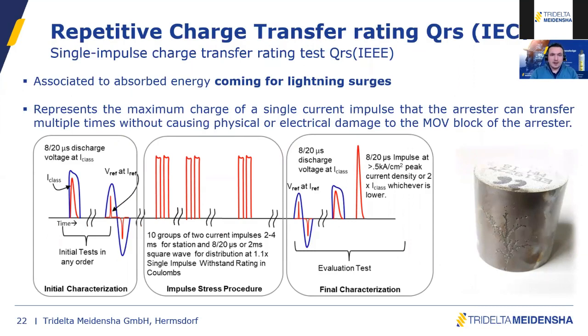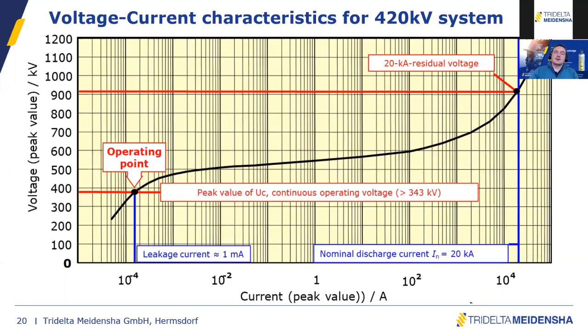Okay, so now come the energy ratings, just to make the transition a little better. As I said, from time to time, and this is the reason why you use surge arresters, you will expect lightning impulses and switching impulses on your system. You have defined a rated voltage, and you have defined the residual voltage that gives you the confidence that your system, your power transformer, your cable termination, your line is protected, okay?